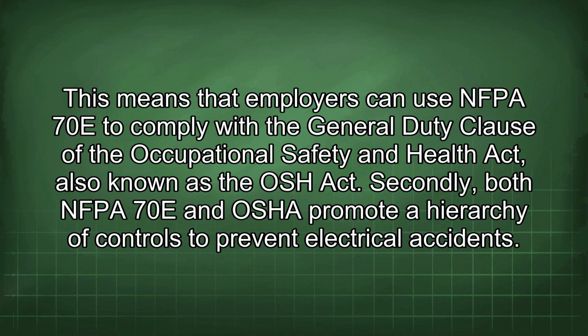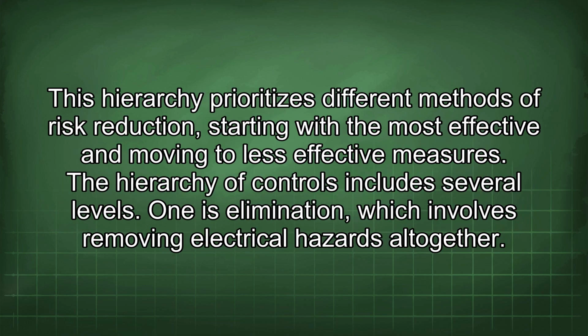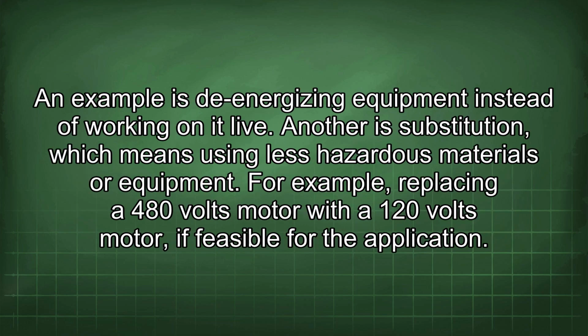Secondly, both NFPA 70E and OSHA promote a hierarchy of controls to prevent electrical accidents. This hierarchy prioritizes different methods of risk reduction, starting with the most effective and moving to less effective measures. The hierarchy of controls includes several levels. One is elimination, which involves removing electrical hazards altogether. An example is de-energizing equipment instead of working on it live.